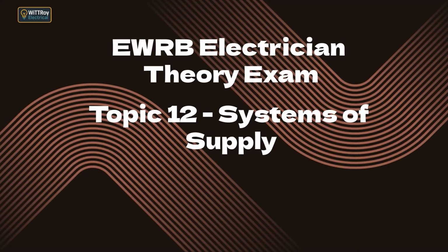Let's begin. 12.1 New Zealand Electrical Supply System. 12.1a. Illustrate with labeled diagrams the New Zealand electrical supply system showing the generation, transmission and distribution systems. New Zealand's supply system starts at generation, where electricity is produced using hydro, geothermal, wind, and gas/steam turbine stations. The generators produce electricity at around 11 to 18 kilovolts. This is stepped up to high transmission voltages, typically 110 kilovolts or 220 kilovolts, for long-distance transmission across the country.